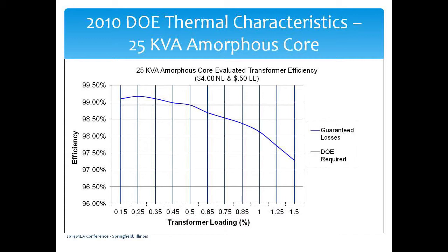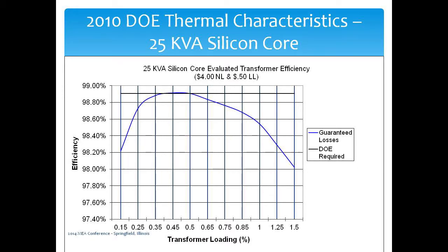You can see where this one on amorphous starts above the efficiency level required by DOE. It actually goes above that and then tapers off above 50% load. It starts to taper downward. Now take a look at this one, and this is a silicon core steel design. Notice the different characteristics of it. You'll see it starts at a lower efficiency, actually ramps up to the 50% load, and then ramps down.